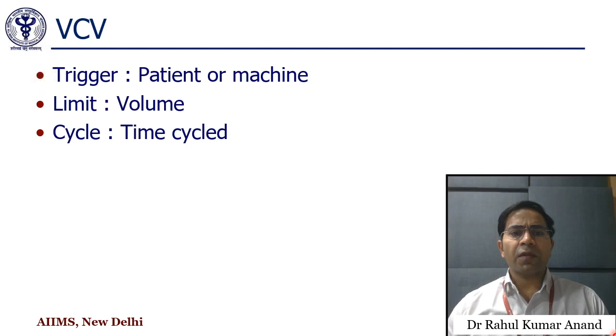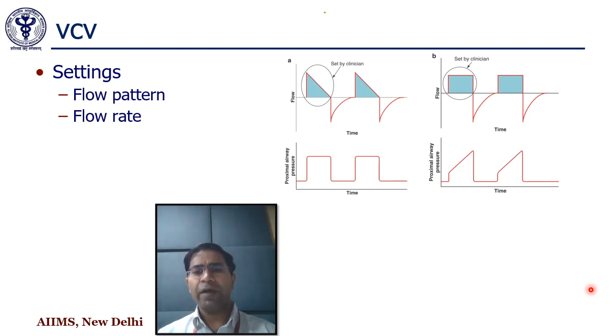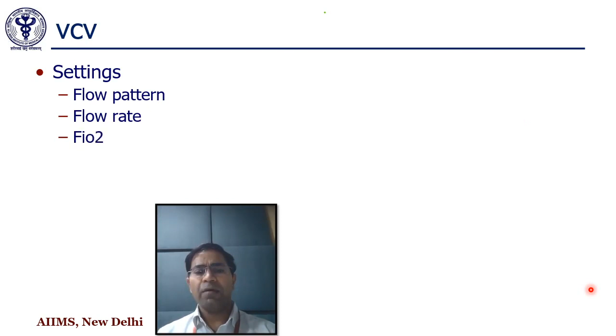If we talk about the settings of volume control ventilation, we choose the flow pattern, and this may be constant, or it may be decelerating, or maybe accelerating. In a few ventilators it is by default constant, and in a few you can choose it. Flow rate may be increased or decreased in a few ventilators, whereas in other ventilators we can increase or decrease it by changing the inspiratory time. FiO2 is usually set at 100% at the time of intubation, then we can decrease it as per the SpO2 of the patient.